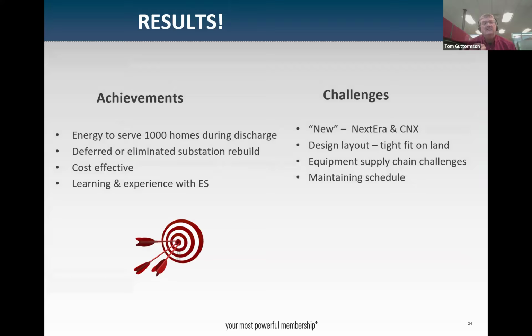That was a cost-effective solution. Doing that to meet the capacity need was less costly than rebuilding the substation. We would have had to replace both of those transformers to achieve the same thing we're able to do with the one battery.